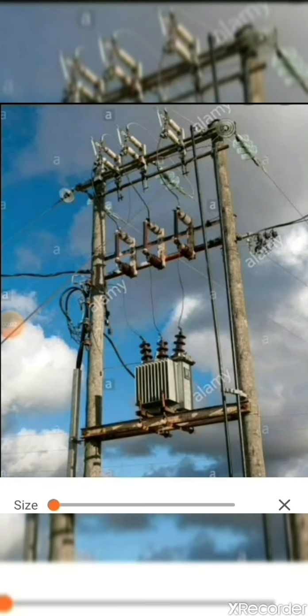We will know about the pole mounted substation and we will do one problem about it. A substation serves as a source of energy supply for the local area of distribution in which it is located. So this is a pole mounted substation, and here we can see two poles and one cross arm. Three incoming wires, R, Y, B, are coming to our transformer, and the output current is taken by a cable.